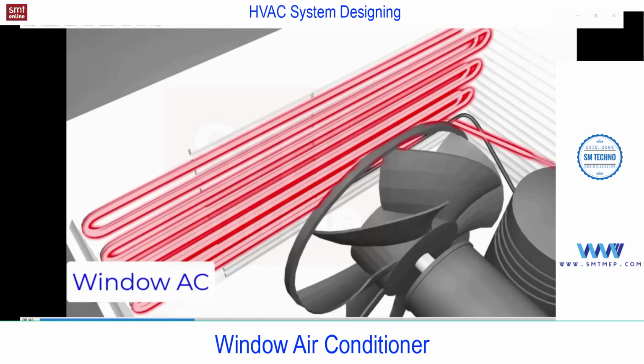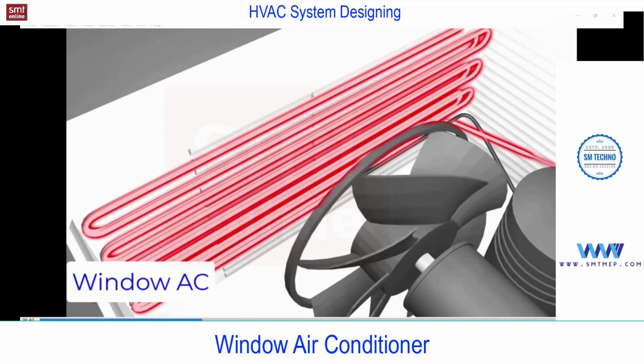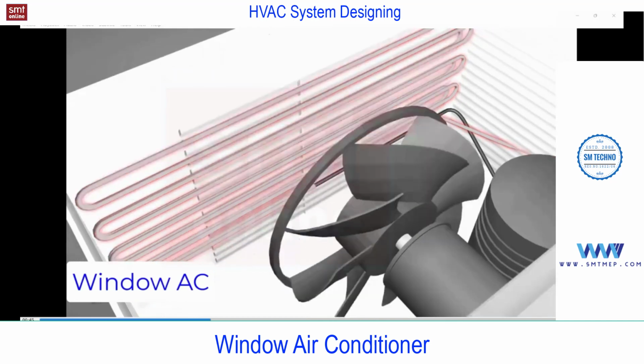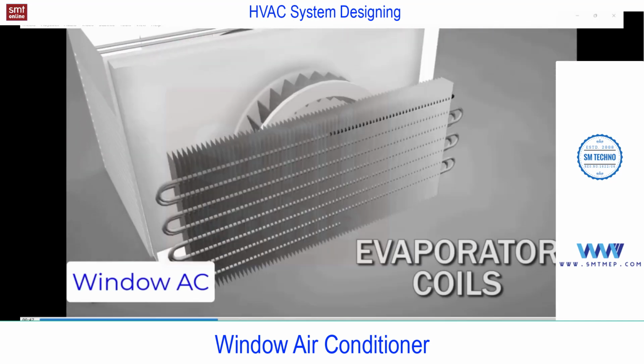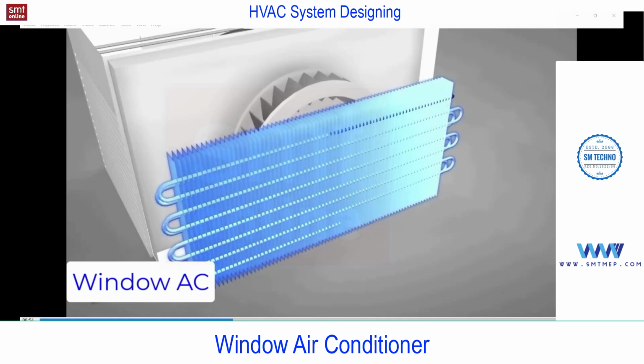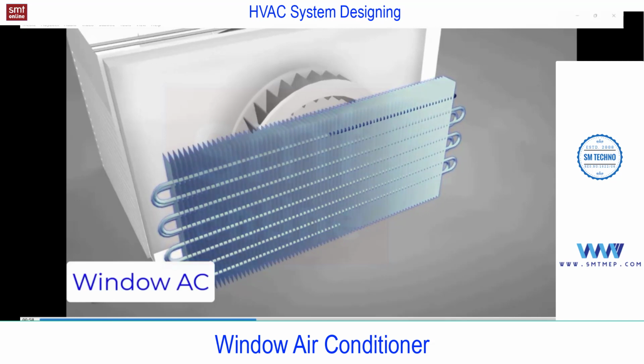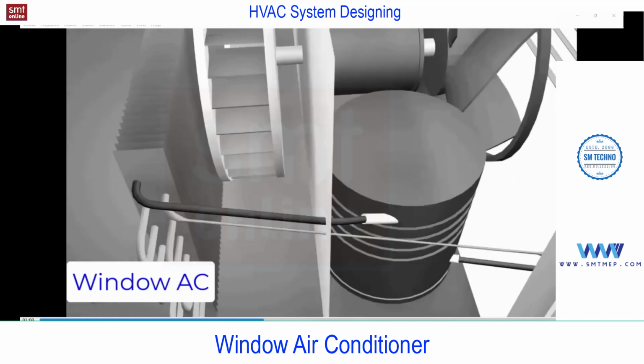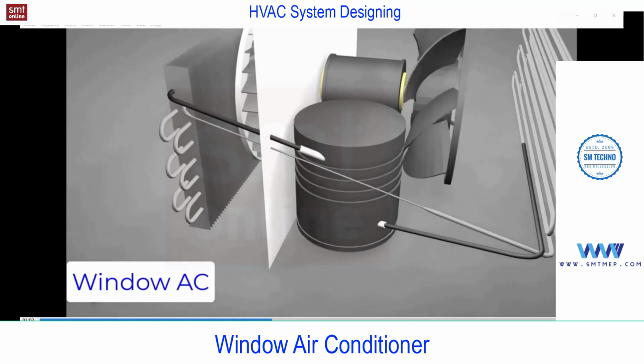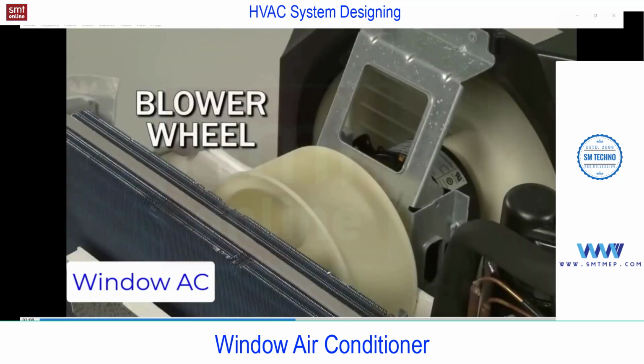Once the refrigerant has passed through the condenser coils and the capillary tube, it travels to the evaporator coils, located near the front of the unit. As the refrigerant liquid enters these coils, it expands into a gas, which makes the coils cold. The gas flows through the coils to a suction line attached to the compressor. The compressor converts the gas back into a liquid, and the cooling cycle continues. At the same time, the fan motor rotates a blower wheel.